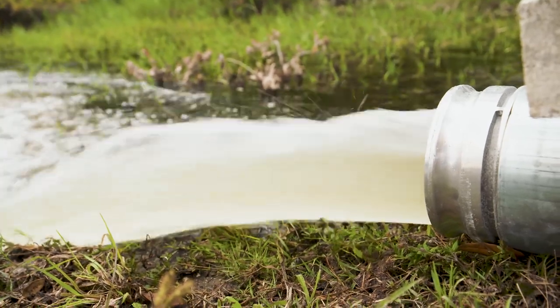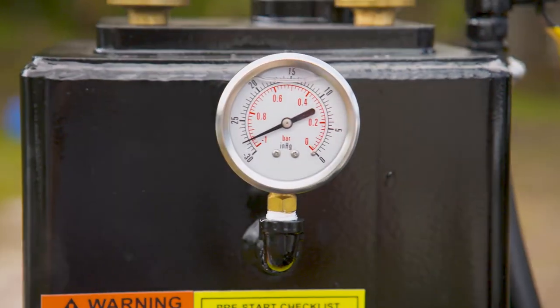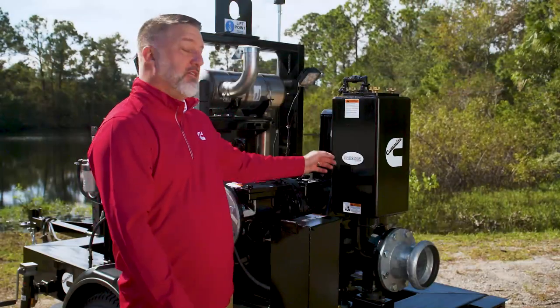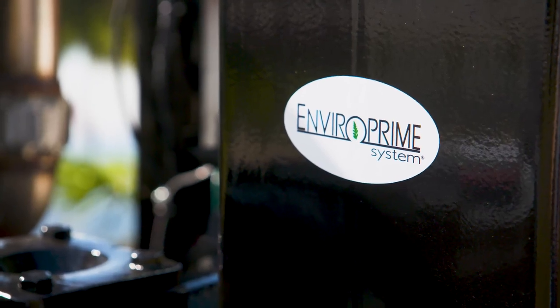The run dry mechanical seal is grease lubricated and has a tungsten carbide rotating face with a silicon carbide stationary seal face. All other components are 304 stainless steel and Viton elastomers. The pump features the EnviroPrime system.